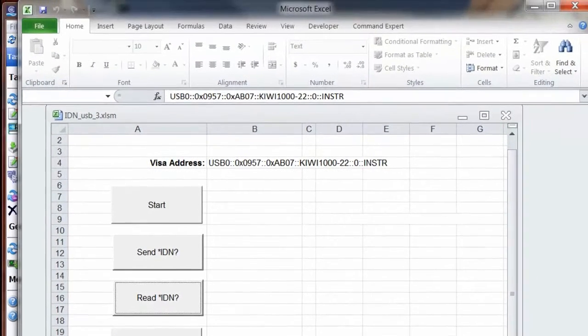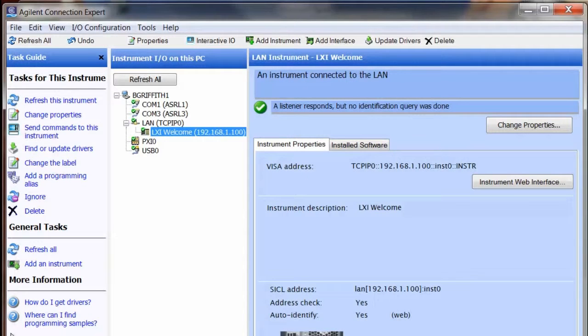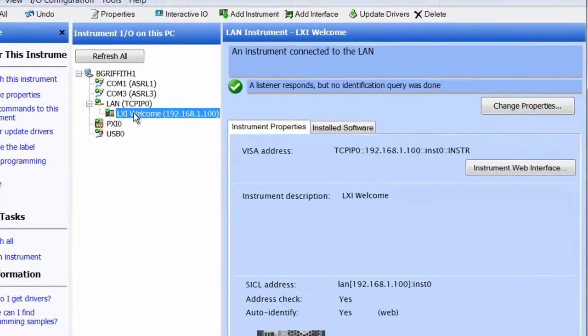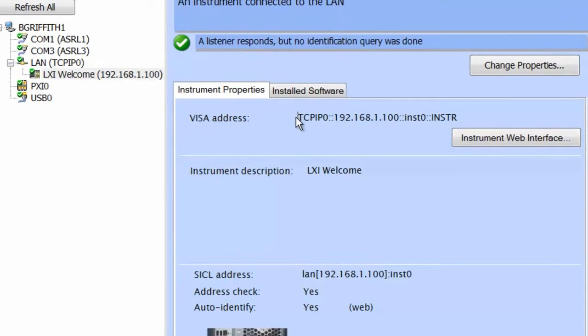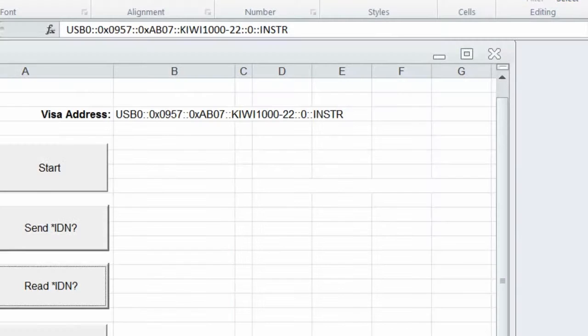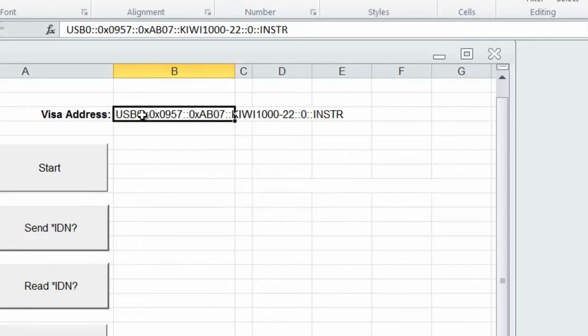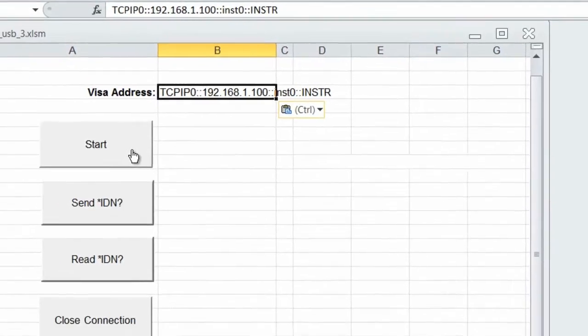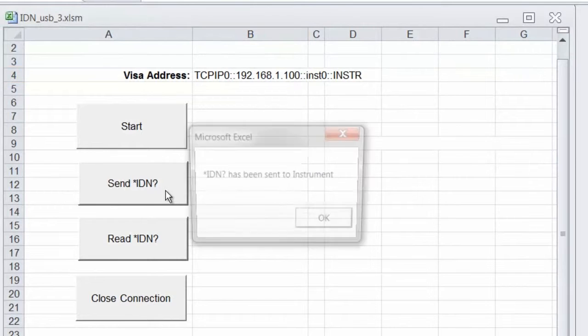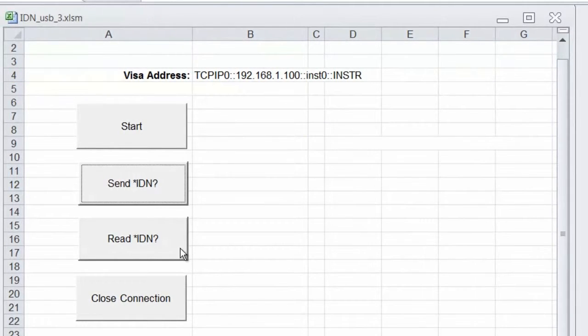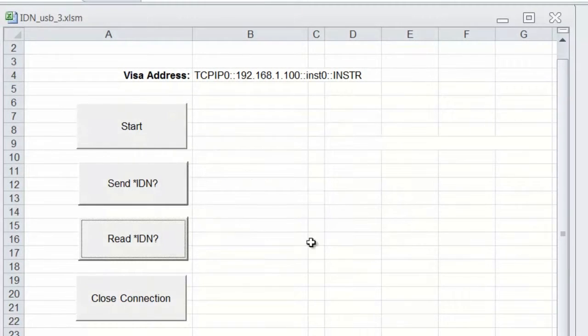I've now installed the LAN cable. We'll go back to the Agilent Connection Expert and on the LAN it's found the instrument. We'll copy the VISA address and drop it into our program. It's just that simple to switch instrument I/O. We'll start our program, send the star IDN question mark, and read back the query from the instrument.